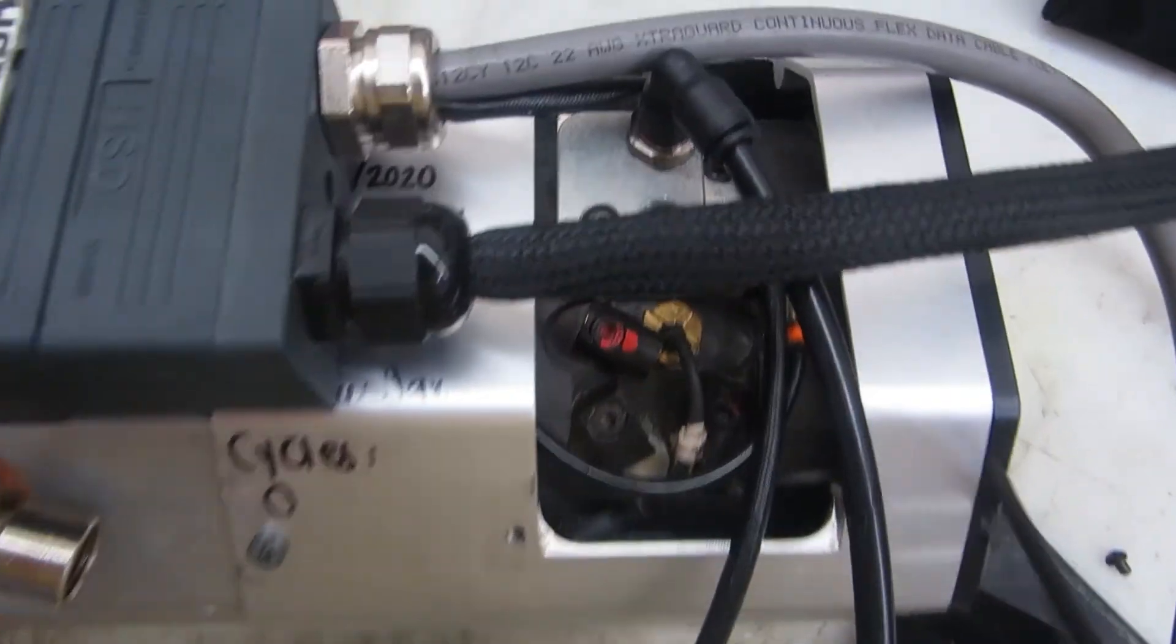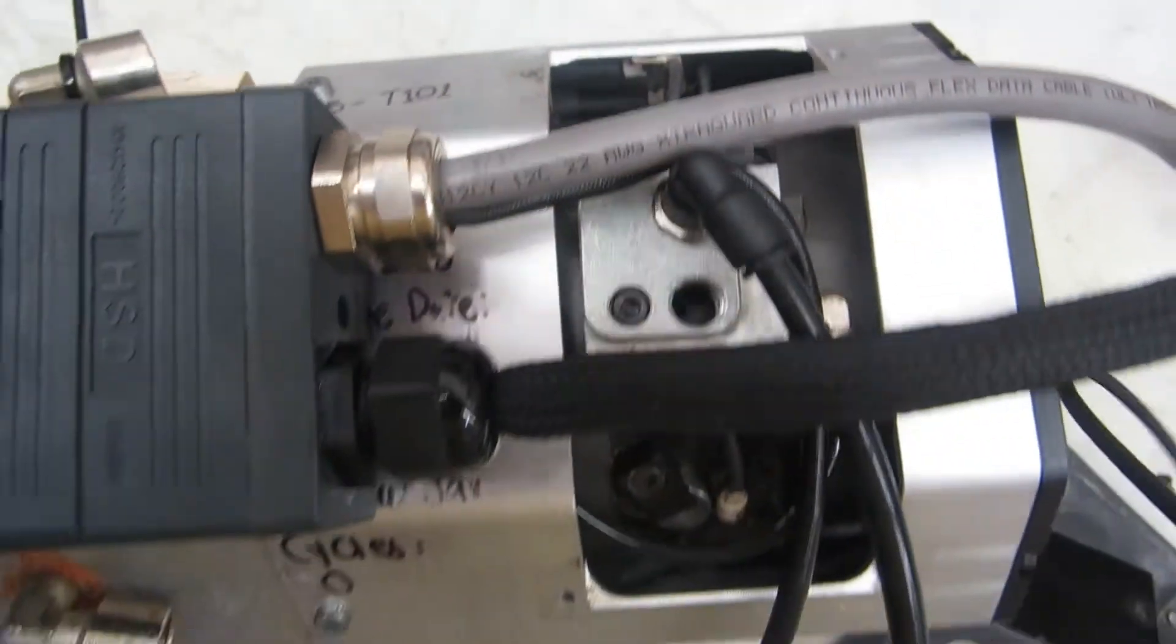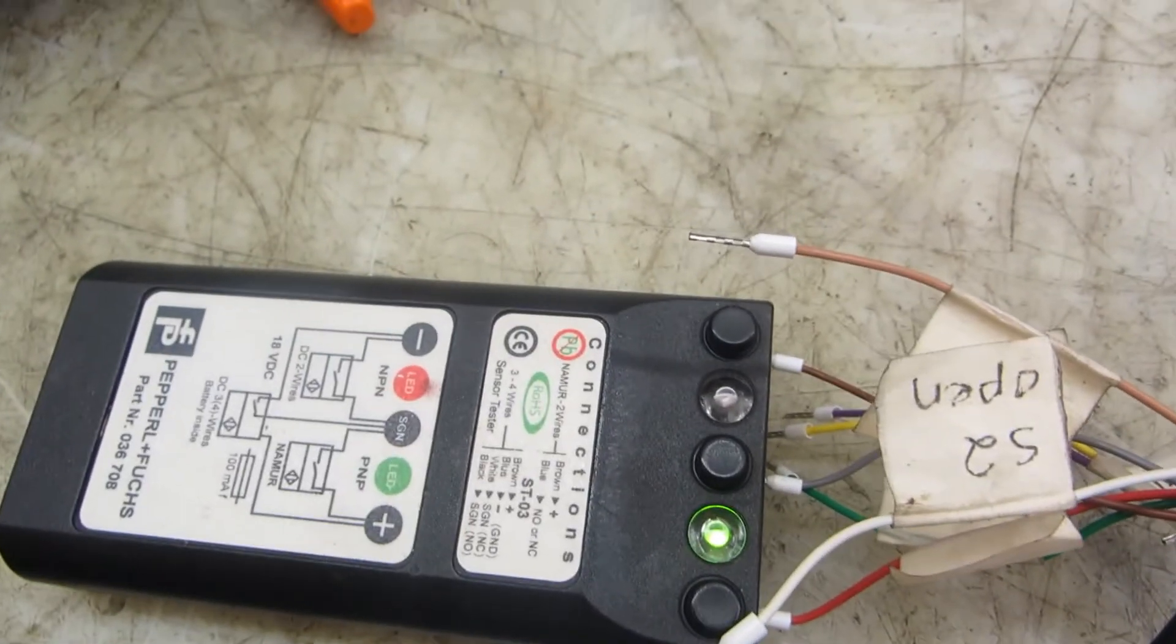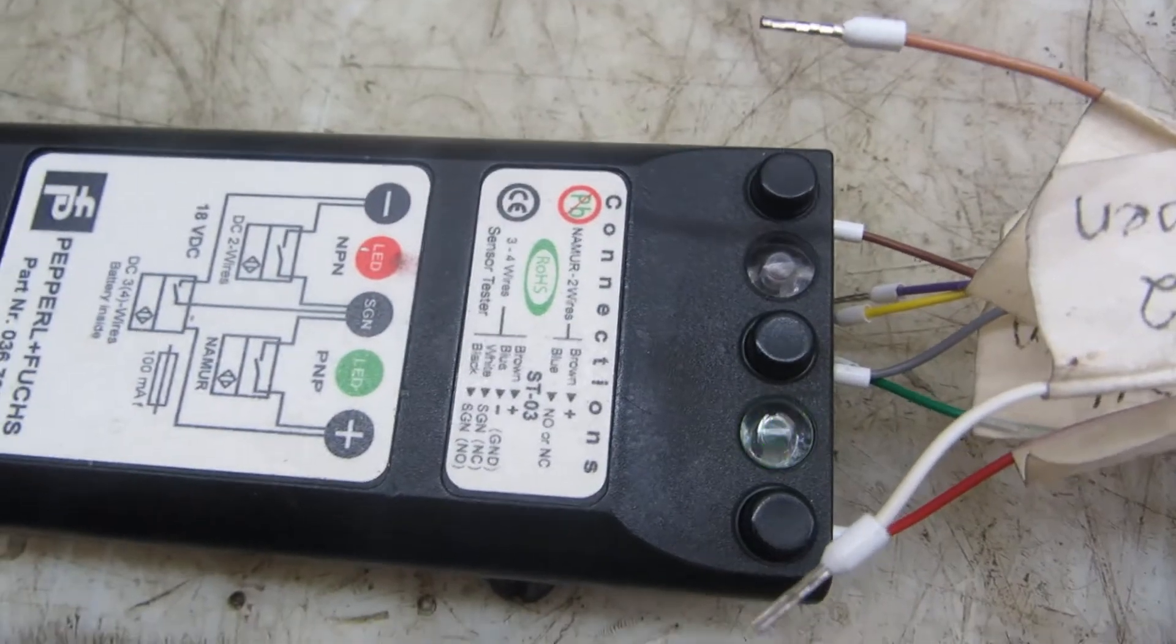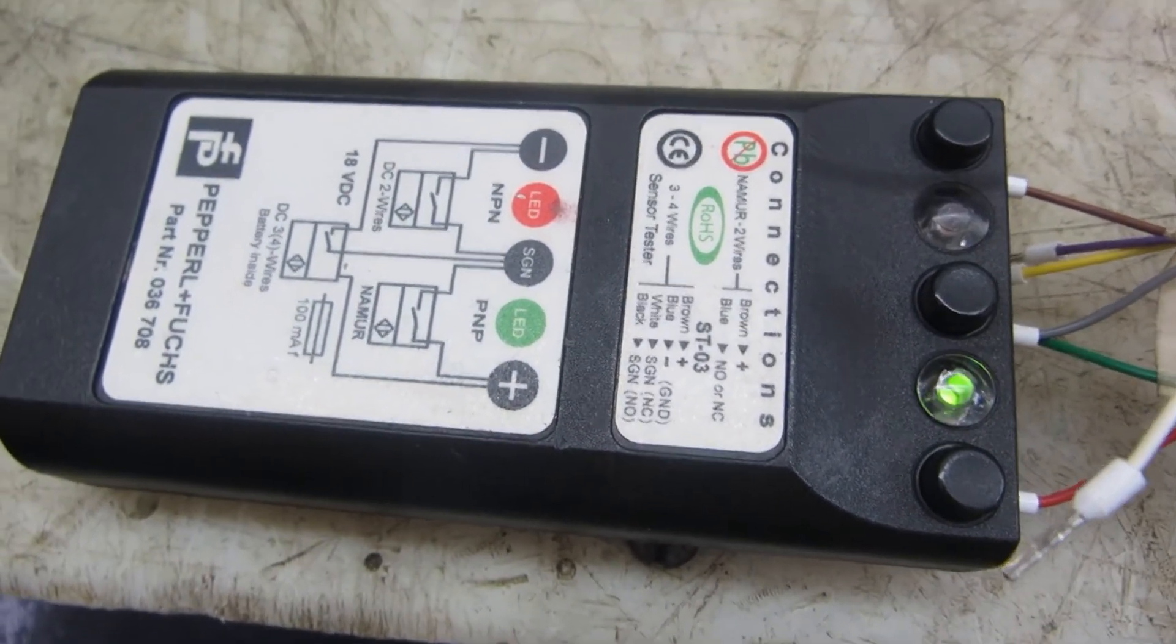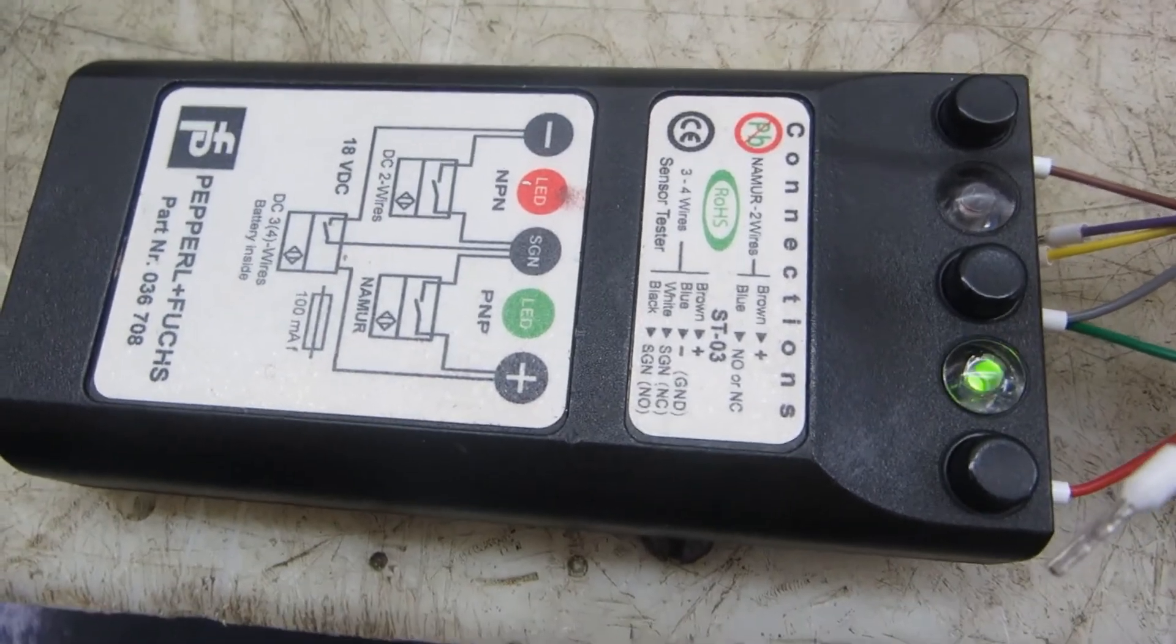Now we're going to show S3. S3 is the bottom sensor on this side here. Hook the meter up to S3 connections and what you do is rotate the shaft. As you rotate the shaft, you'll get a pulse. You'll see the green light pulsing. That shows you that S3 is reading correctly.